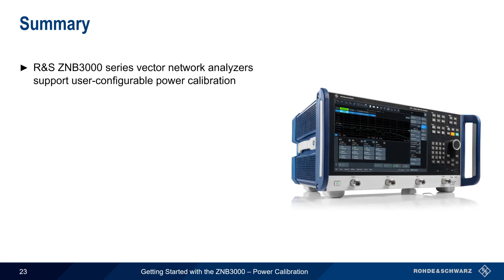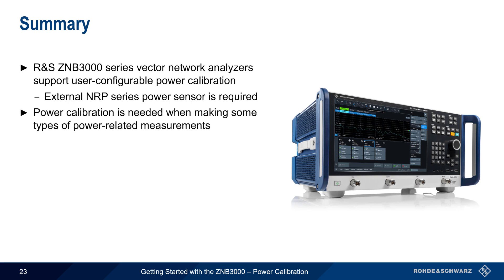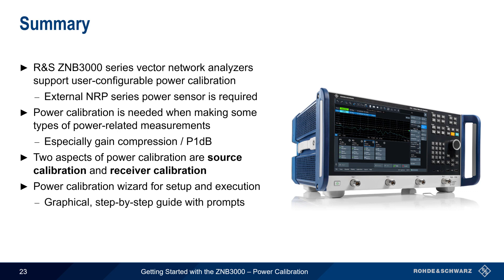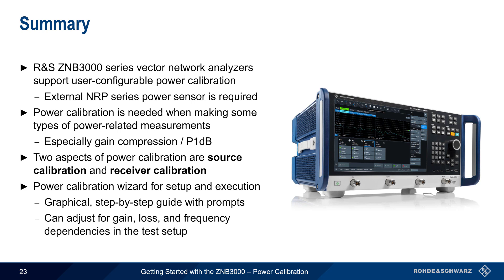In summary, Rohde & Schwarz ZNB3000 Series Vector Network Analyzers support user-configurable power calibration, typically performed using an attached NRP Series power sensor. Power calibration is needed when making power-related measurements, particularly when measuring gain compression or P1dB. The ZNB3000 supports both source calibration and receiver calibration. The power calibration wizard makes it easy to set up, configure, and run power calibration with a graphical step-by-step guide. Power calibration configuration can also be adjusted for any gain, loss, and frequency-dependent behavior in the test setup.